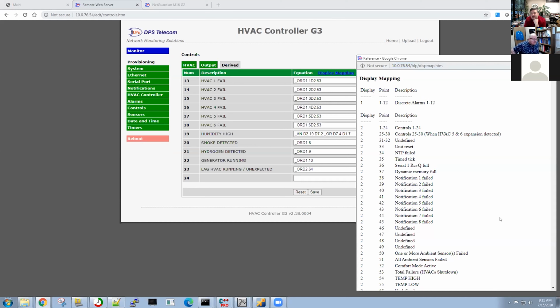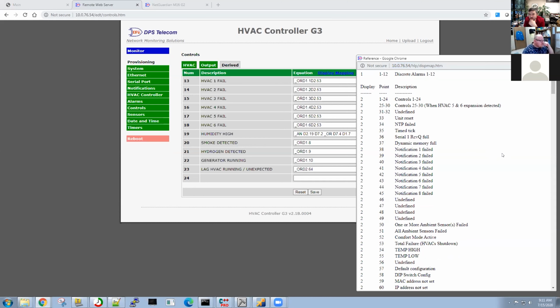So it's a little bit interesting, our syntax, but you can see it starts with an O underscore OR - that's an OR command. So it's saying if display 1.1 or 2.53 are set, then this control relay is going to latch and it's going to send a signal back to the NOC center, the original application.